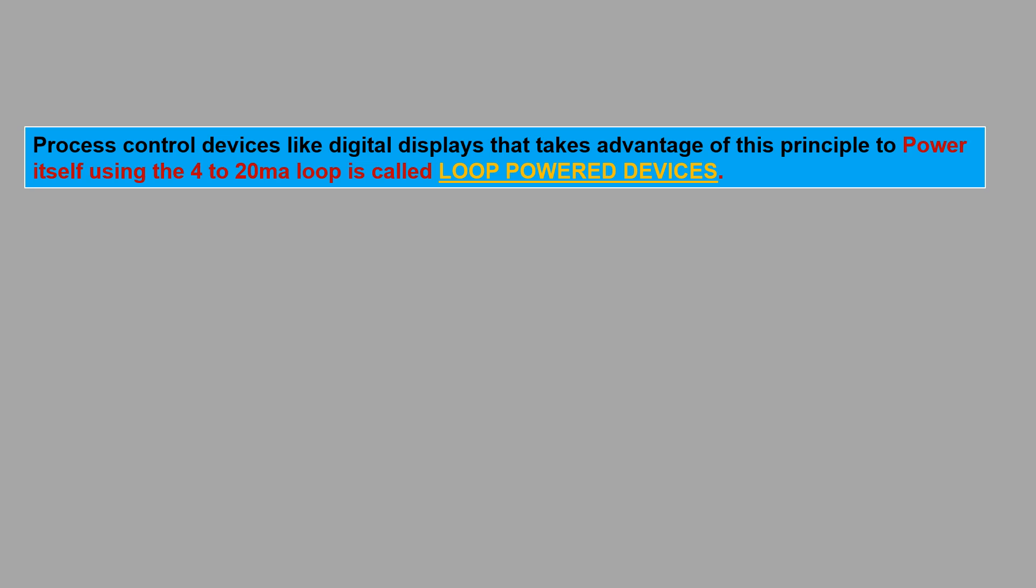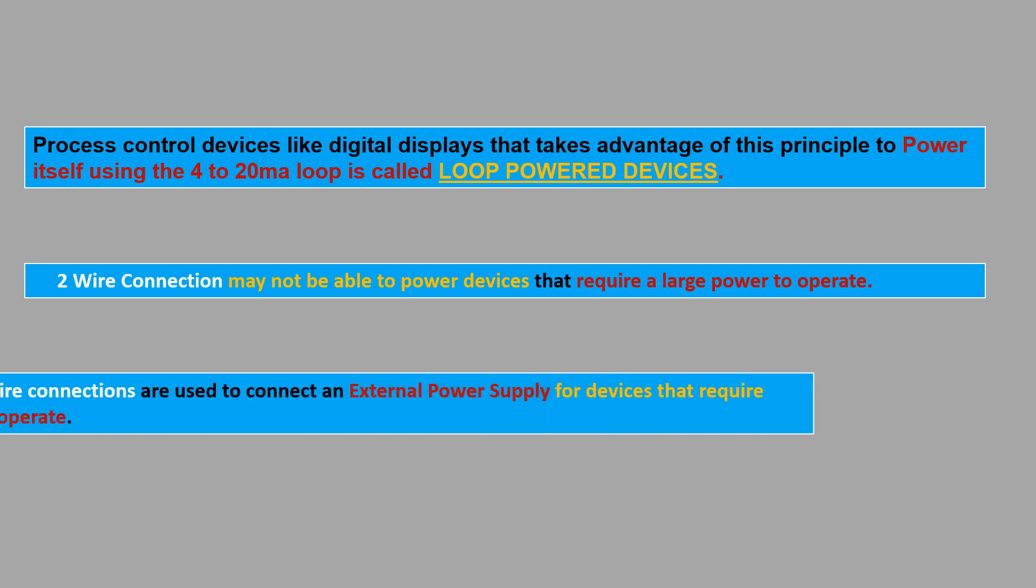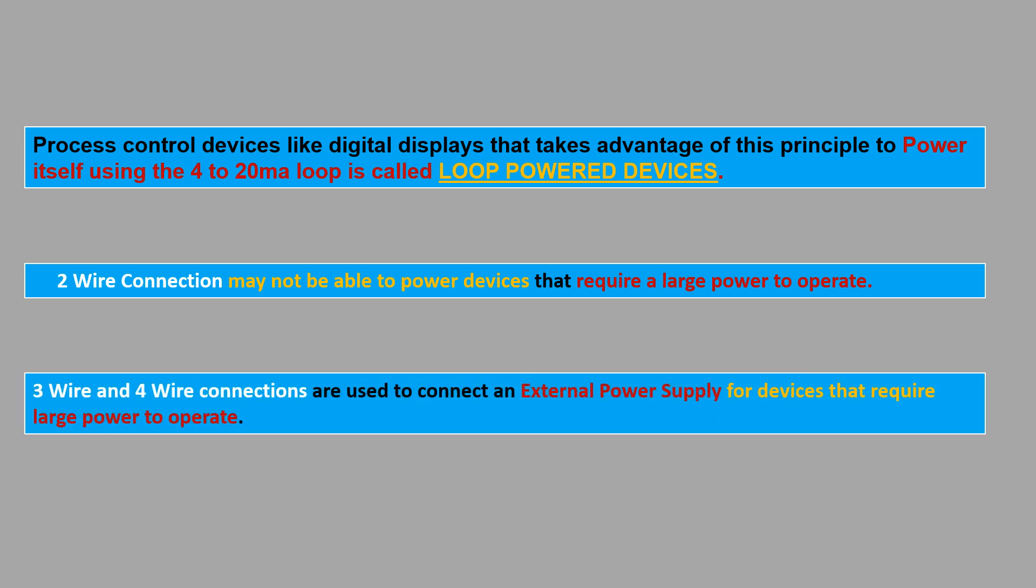Loop-powered instruments consume very little power in order to be able to operate with the power supplied to the loop. A 2-wire connection may not be able to power devices that require a large power to operate. So, a 3-wire or 4-wire connections are used to connect an external power supply for devices that require large power to operate.